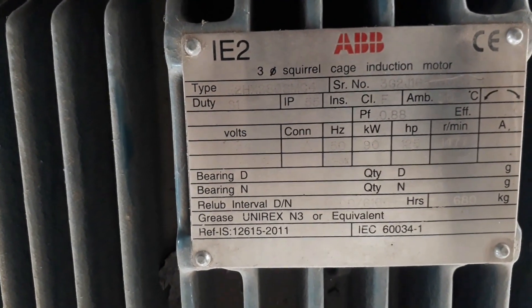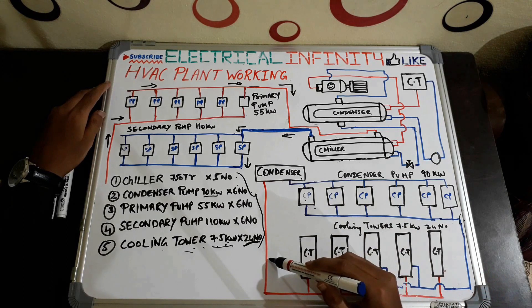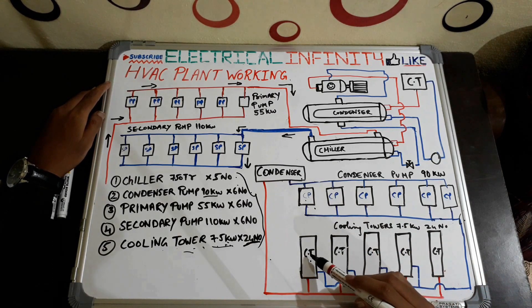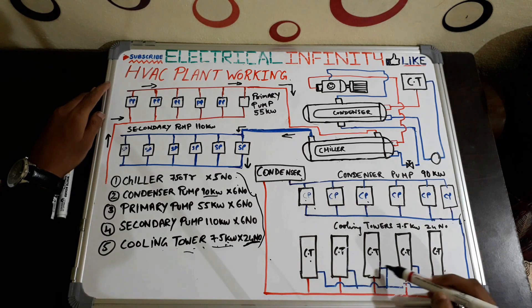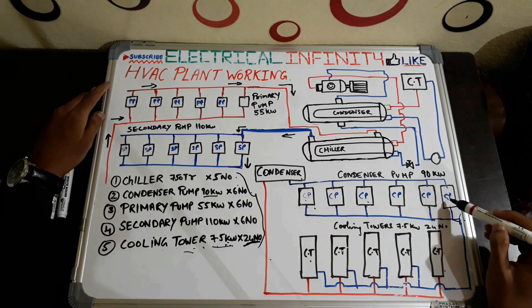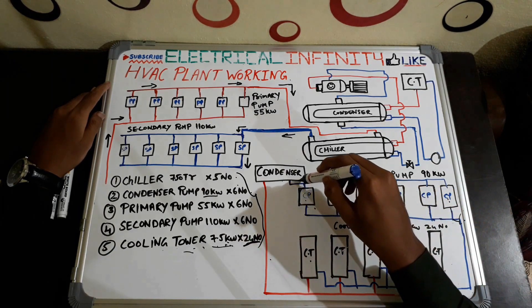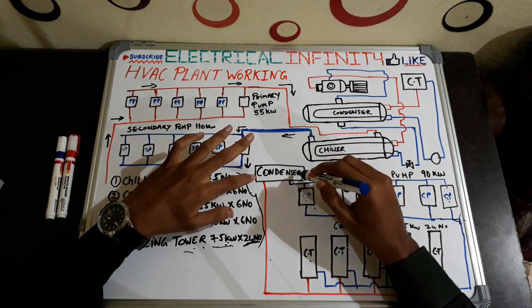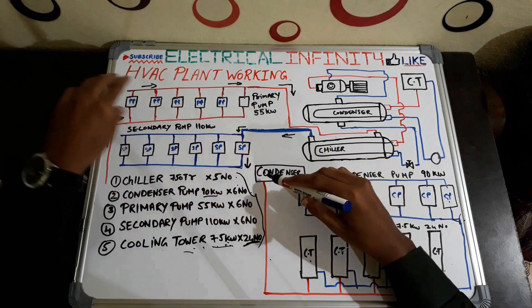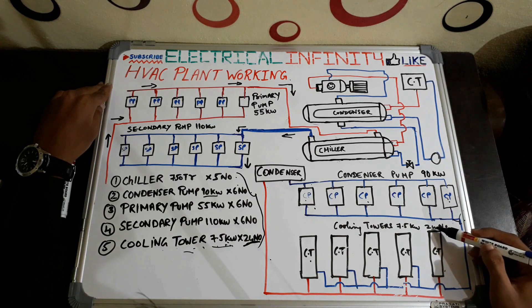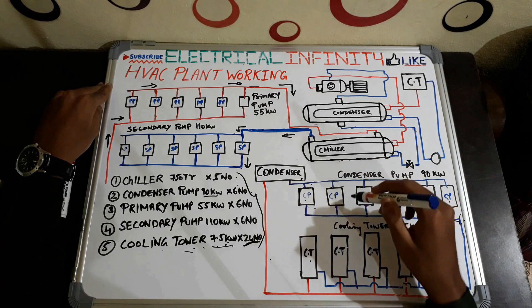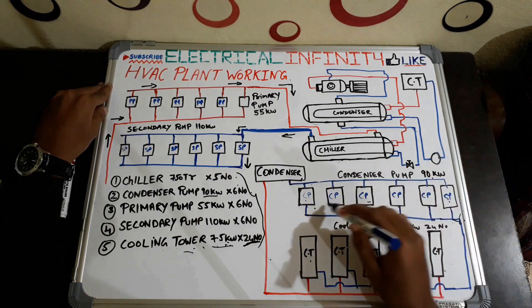Here you can see the condenser, condenser pump, and cooling tower. Red lines mean hot water and blue lines mean cool water. The cool water from the cooling towers is pumped into the condenser via the condenser pump. Heat exchange takes place between the cool water and the condenser refrigerant — the water gets heated up and the refrigerant gets cooled. The heated water is then transferred back to the cooling tower.